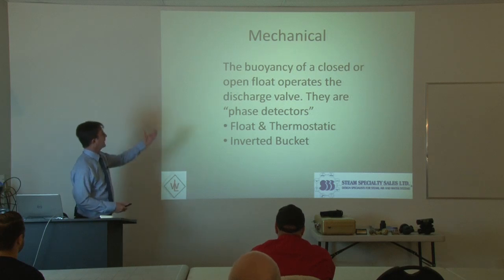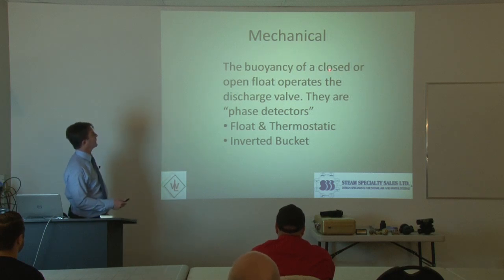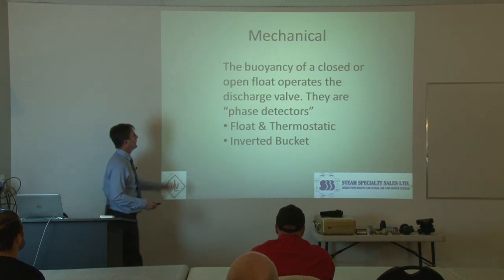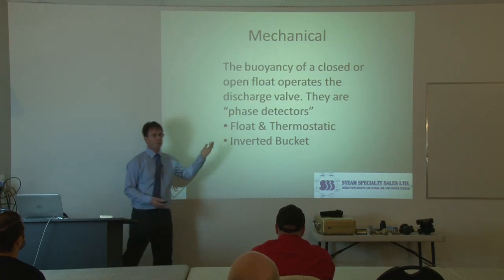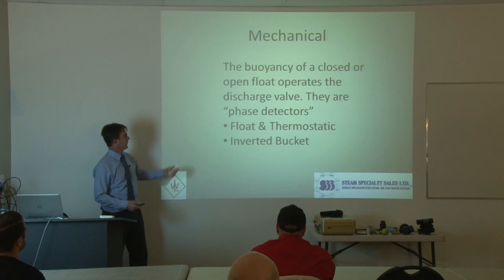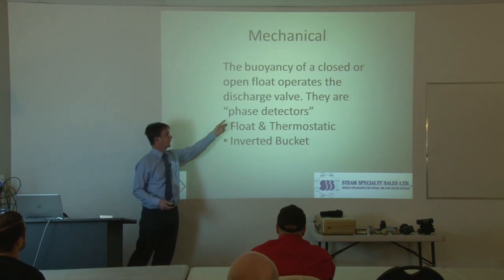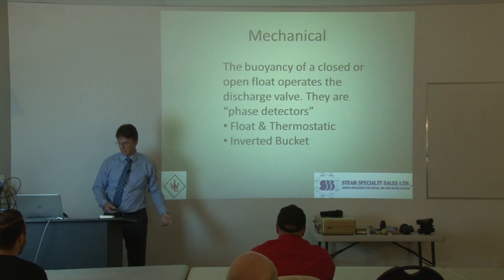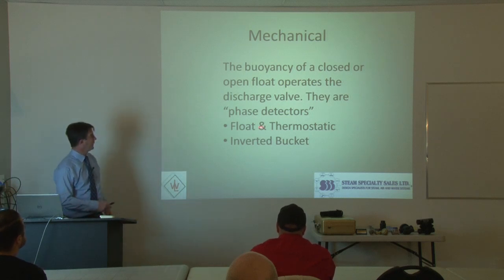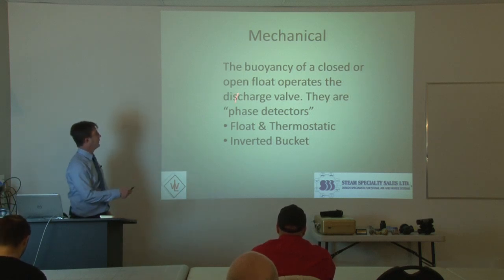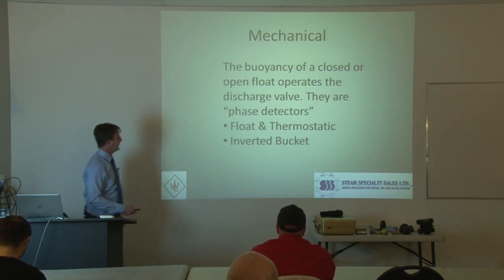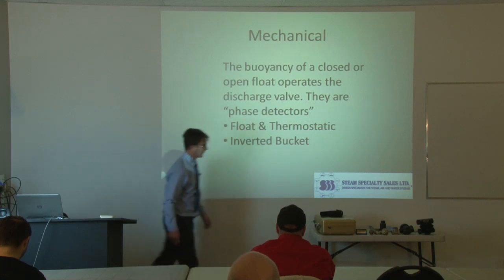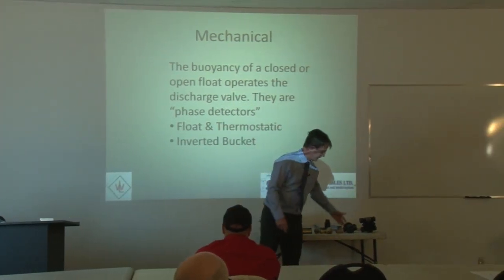The mechanical type of steam trap uses the buoyancy of a closed or open float to operate the discharge valve. They are a phase detector — the operating device knows the difference between condensate and steam, between the liquid phase and the vapor phase. Within the mechanical family, there's the float and thermostatic and the inverted bucket.